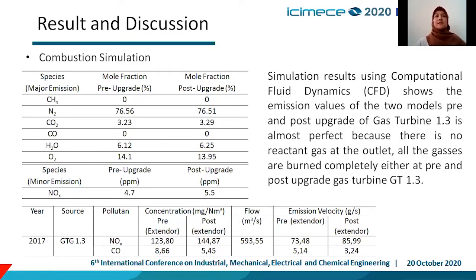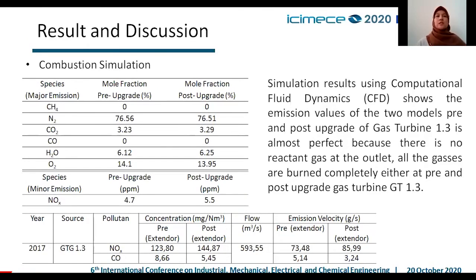First, you can see the combustion simulation using CFD for the pre-upgrade condition and post-upgrade condition. For the major emissions, the mole fraction between pre-upgrade and post-upgrade is almost similar. We can say that the combustion process at pre-upgrade and post-upgrade is nearly perfect. We can see from the CO parameter that the concentration is 0%.